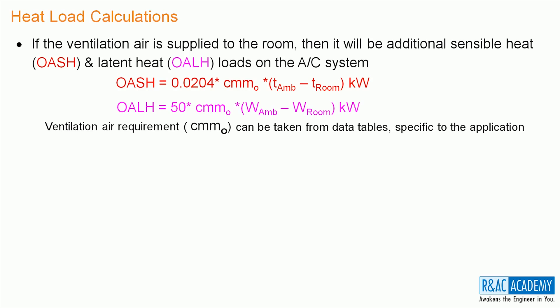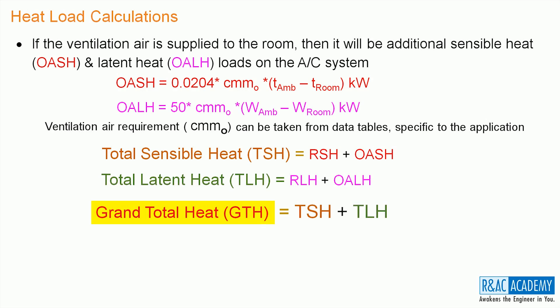After computing OASH and OALH, we will get the total sensible heat load equal to RSH plus OASH, and total latent heat equal to RLH plus OALH. And finally, we have the grand total heat which is equal to TSH plus TLH.